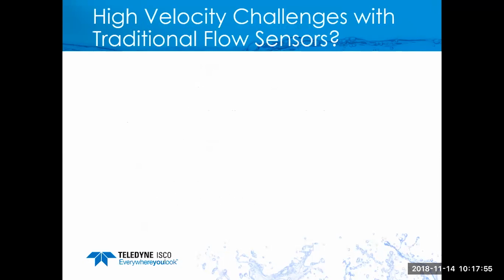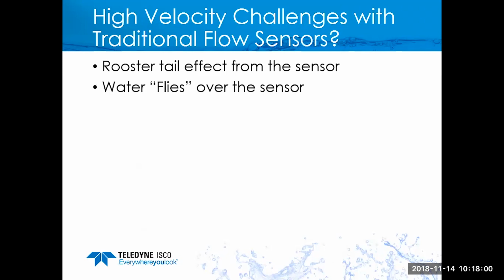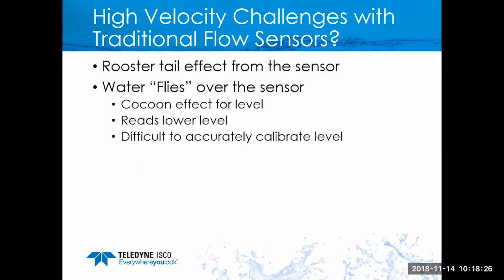All right, so let's take a look at some of the challenges with traditional flow sensors. You're going to have this rooster tail effect over the sensor. Pretty much water is going to hit it and fly over the top of it, so it's like a cocoon effect. In that case it will read lower level. One common thing people will do is take a standard area velocity sensor, zero it in air, and put it in a pipe. If that water velocity is pretty high, typically anything over about 3 to 4 feet per second, you're going to have an effect on the level, so it's going to read a little bit low.